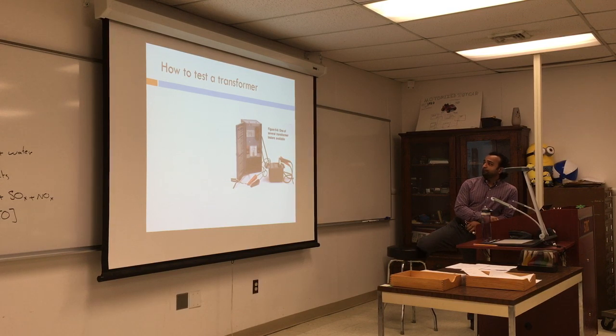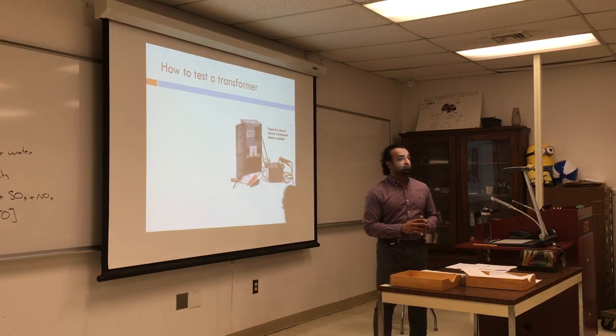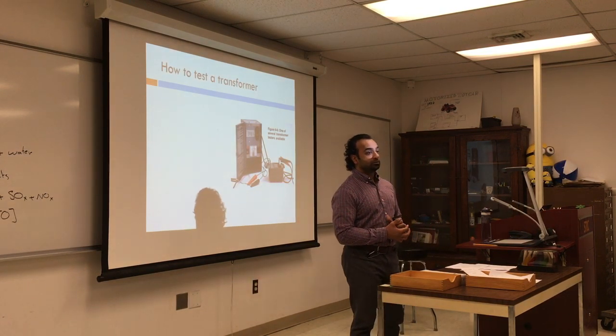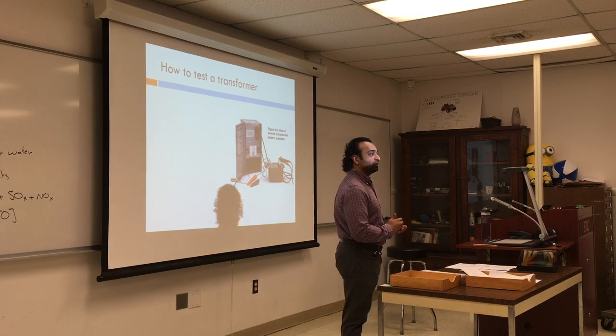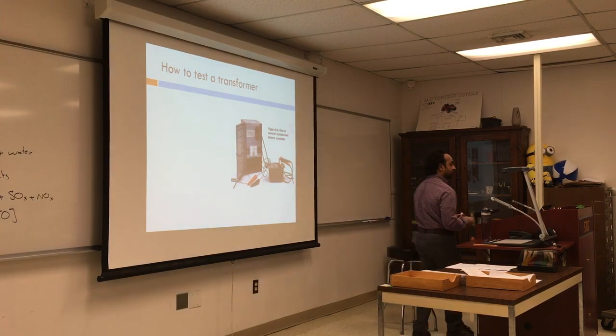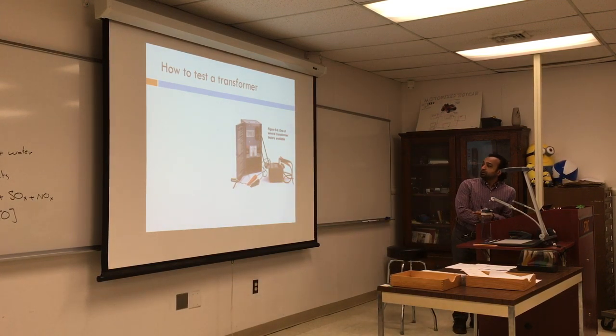So this one is the tester, the test voltage. Can you test your transformer using your voltmeter? No, don't do that. What is the limit for your voltmeter? 600 volts is the upper limit. You don't go above that. So you need a special tool to measure the transformer. Even our little sticks, I think the max is 600 too. They just give you a red light, but you don't see much.